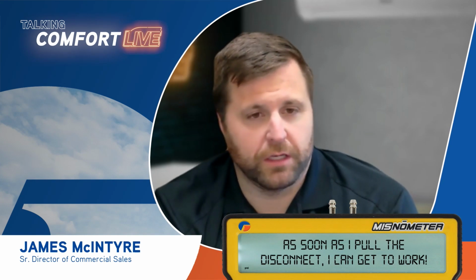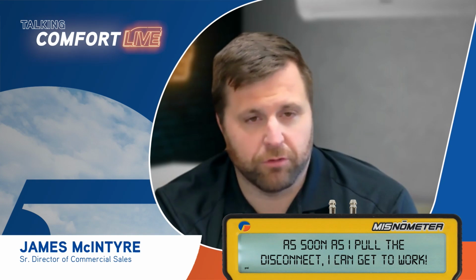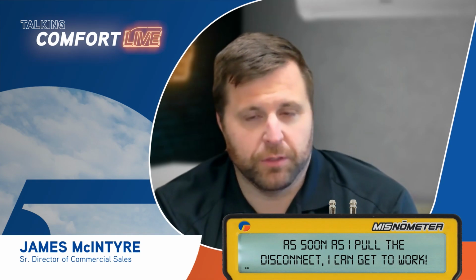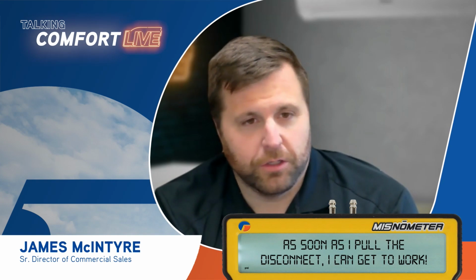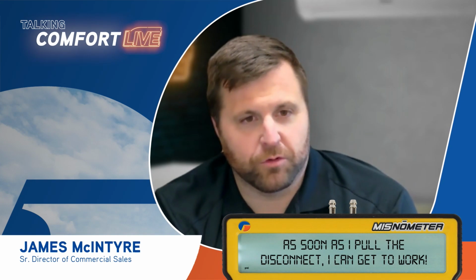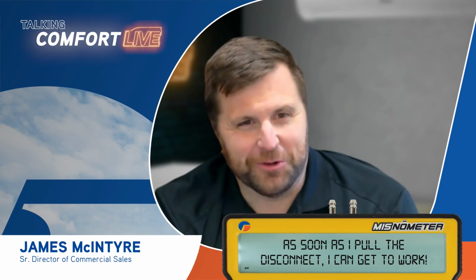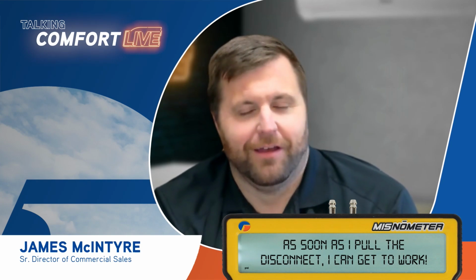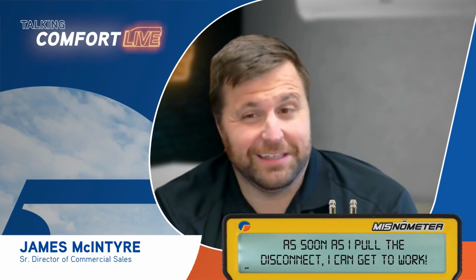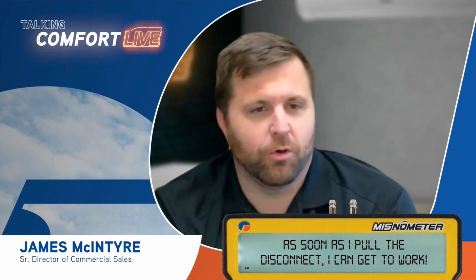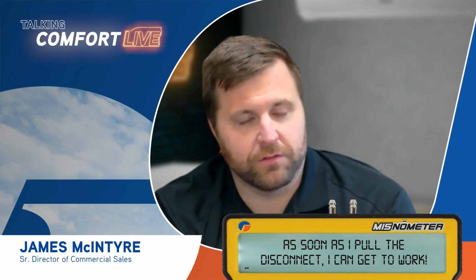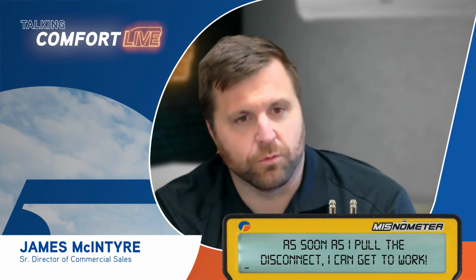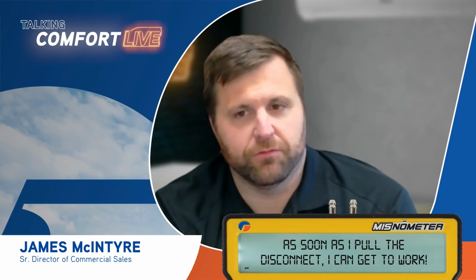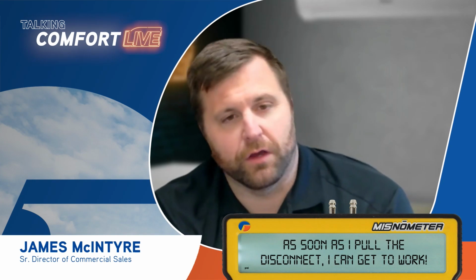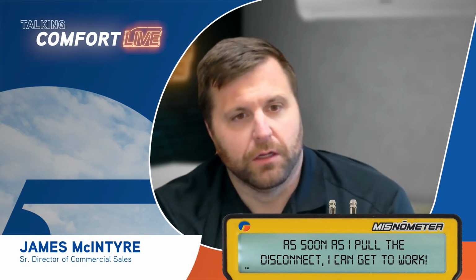Many manufacturers will tell you 10 minutes, 15 minutes, 20 minutes, whatever. If I told you that flipping a light switch, wait 15 minutes before you start messing around with that light socket, you would probably verify that there's no voltage on it, right? So instead of waiting that long, go ahead and test it, because it can take as little as 20 seconds to discharge to a safe level.